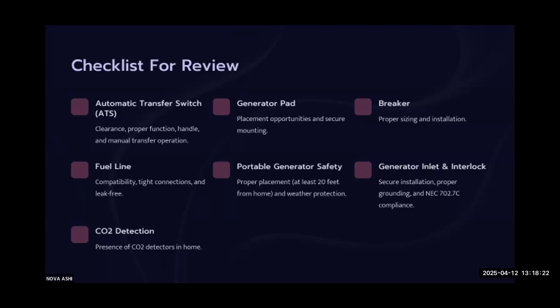Of course, make sure you have CO2 detection, a nice generator pad, leveled and placed properly, and check your breaker sizing. Portable generators are suggested to be 20 feet away from the house, with your generator inlet and interlock. I also suggest reading the National Electric Code, a few more code suggestions being 250, and of course generators at 445.